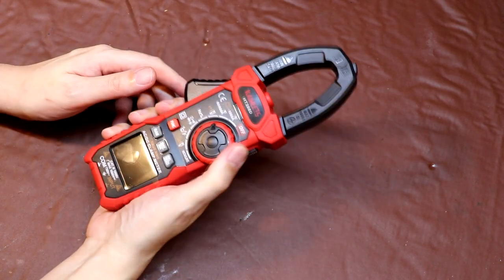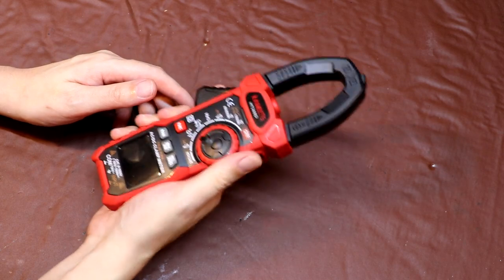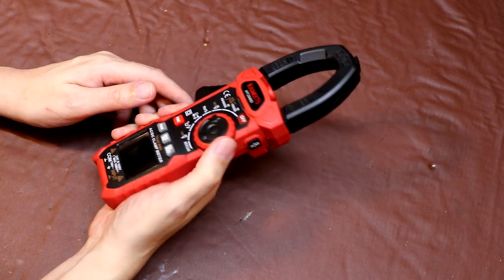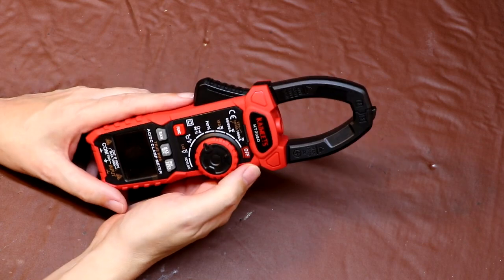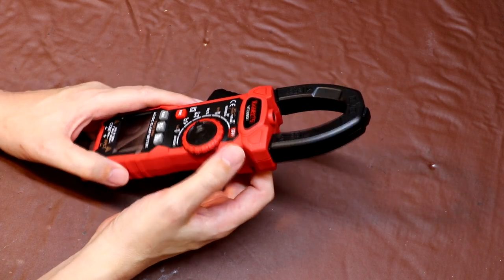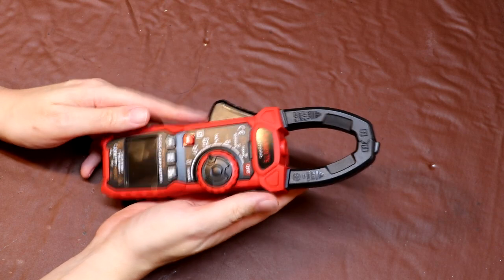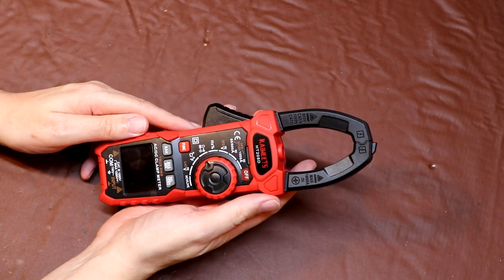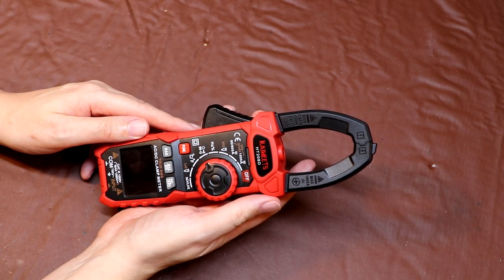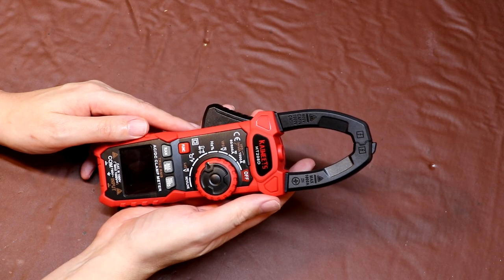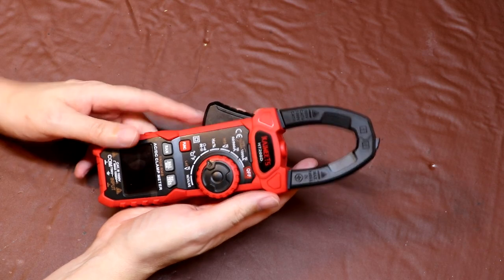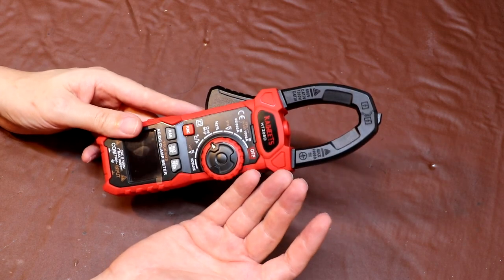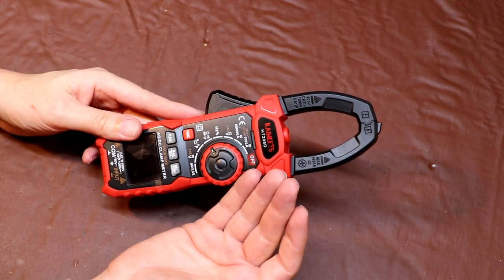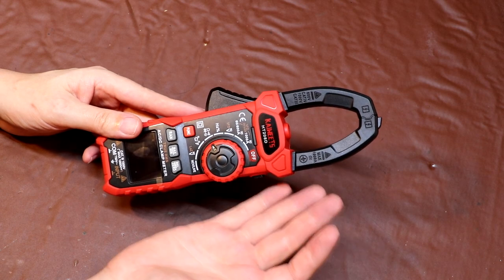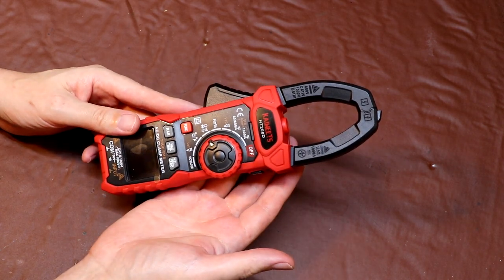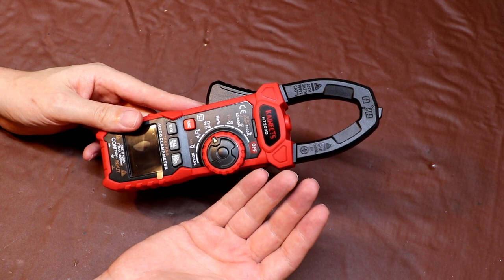So I've just washed my hands. Yeah, that's a lot better. But what I would say, if I was using this meter in an industrial situation, and the sort of thing I would be using this for is maybe if I was doing some maintenance on a system that had large electric motors on it, something like that. It's quite likely if I've just changed a motor or done something, I'm going to have grubby, dirty, oily hands. Now I'm not going to bother to go and wash my hands before I make any current measurements. I'm just going to get the meter out and use it. The other thing is I might be wearing gloves.